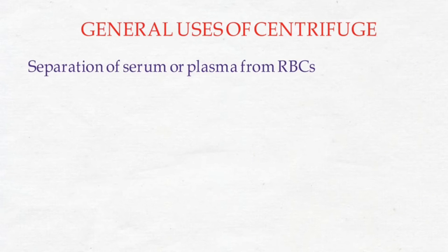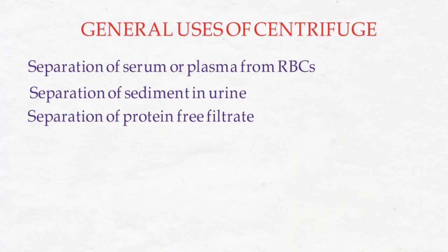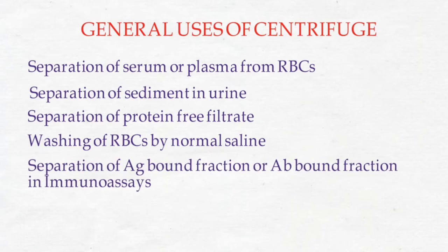The general uses of a centrifuge include: separation of serum or plasma from RBCs; separation of sediment in urine; separation of protein-free filtrate; washing of RBCs with normal saline; and separation of antigen-bound or antibody-bound fractions in immunoassay.